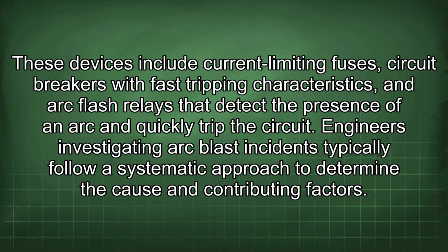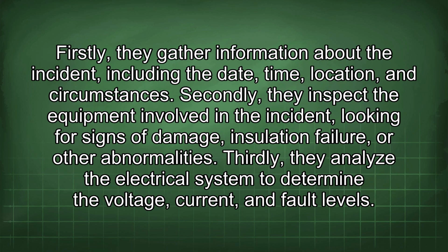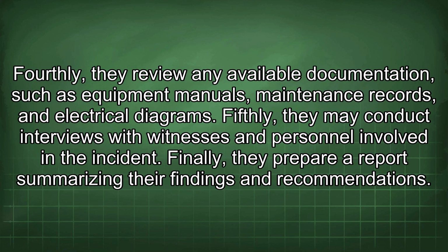Engineers investigating arc blast incidents typically follow a systematic approach to determine the cause and contributing factors. Firstly, they gather information about the incident, including the date, time, location, and circumstances. Secondly, they inspect the equipment involved in the incident, looking for signs of damage, insulation failure, or other abnormalities. Thirdly, they analyze the electrical system to determine the voltage, current, and fault levels. Fourthly, they review any available documentation, such as equipment manuals, maintenance records, and electrical diagrams. Fifthly, they may conduct interviews with witnesses and personnel involved in the incident. Finally, they prepare a report summarizing their findings and recommendations.